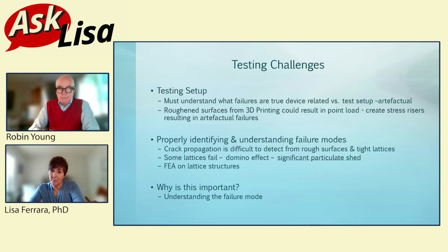That brings me to my second point, and I always discuss this because folks will say, oh, well, it failed. But did it fail in a way that was really related to the device, or is it from your test setup? Always, always, always, with the engineers we teach, assess your test setup. For instance, with rough surfaces, you can point load that implant, because your surfaces are not all at one specific, repeatable amplitude. There's macro, micro, and nano texture to this.